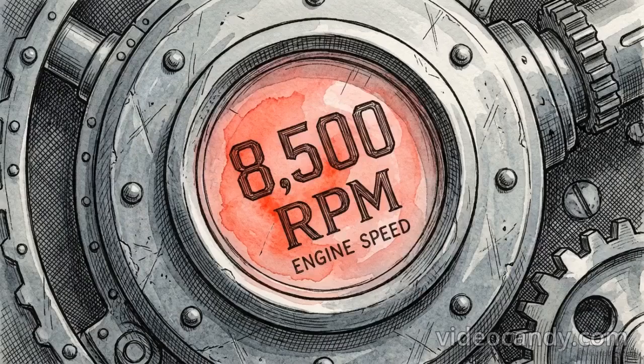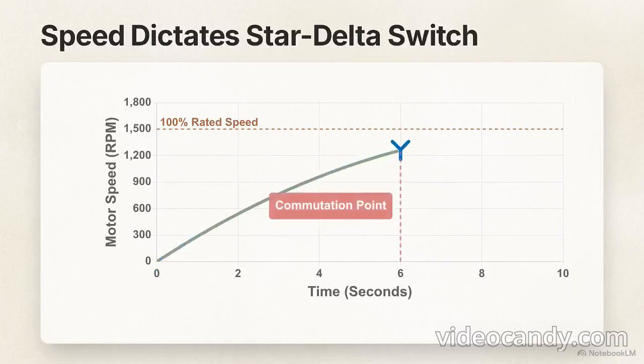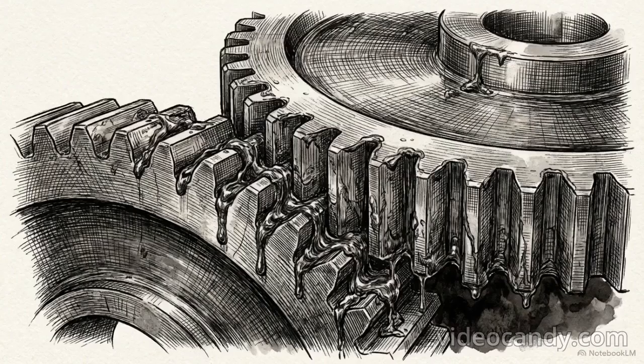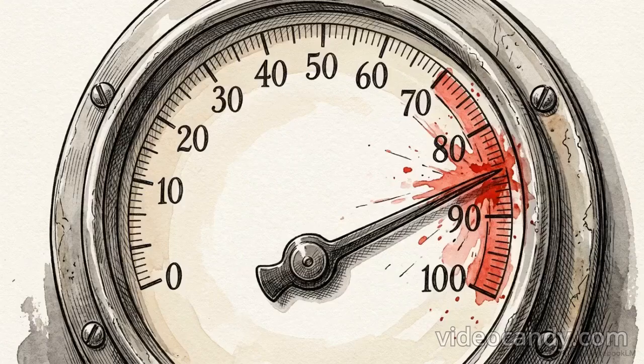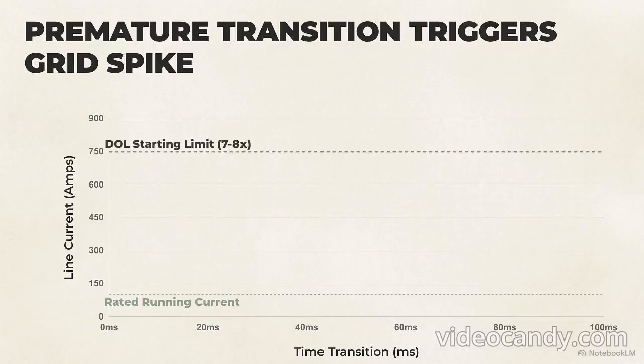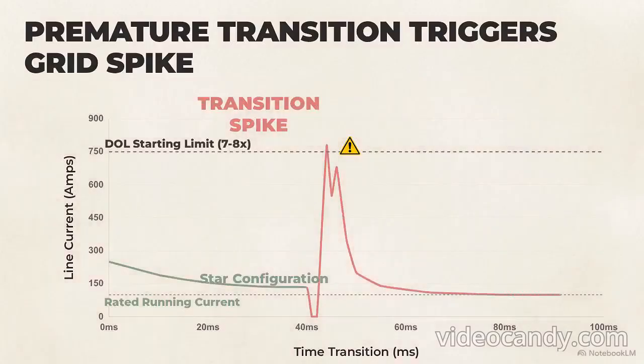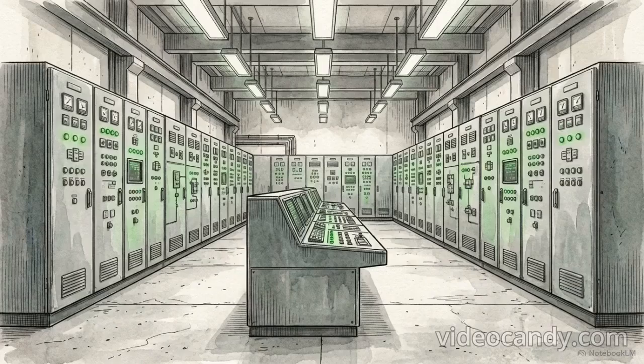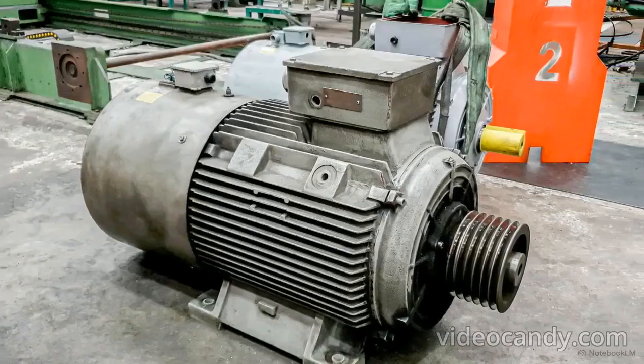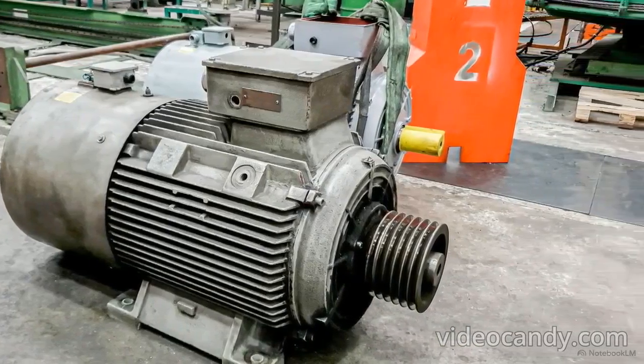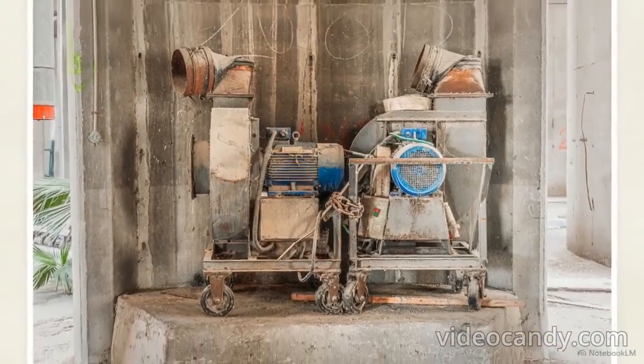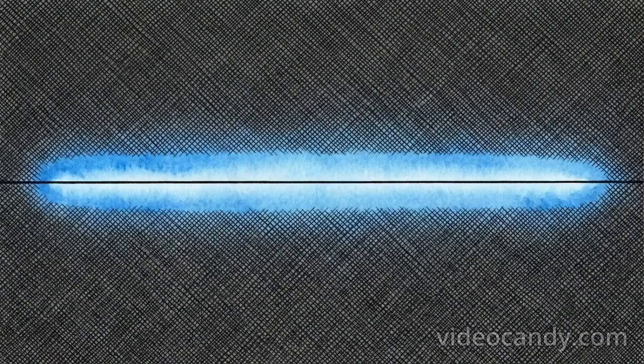Looking at this engineering documentation, the performance formulas confirm the specific math. Because the torque is a function of the voltage squared, the star connection mathematically guarantees this severe drop in rotational force. Operators must carefully calculate the commutation point. This is the exact RPM threshold where the motor must abandon the star connection and switch to delta in order to overpower the rising resistive torque of the load. Timing is unforgiving. Transitioning to delta too early or too late induces a massive transition spike, a secondary current surge that hits the grid almost as hard as a raw direct online start, defeating the purpose of the starter entirely.